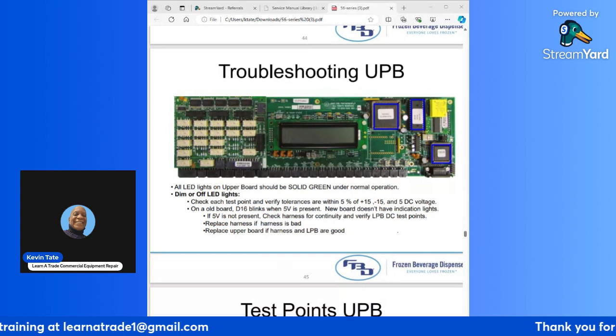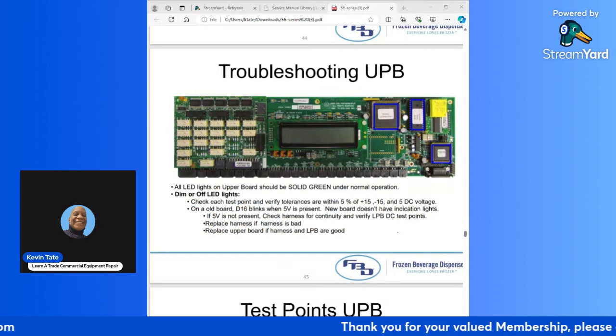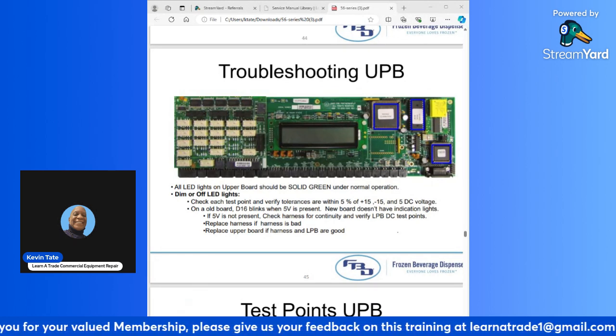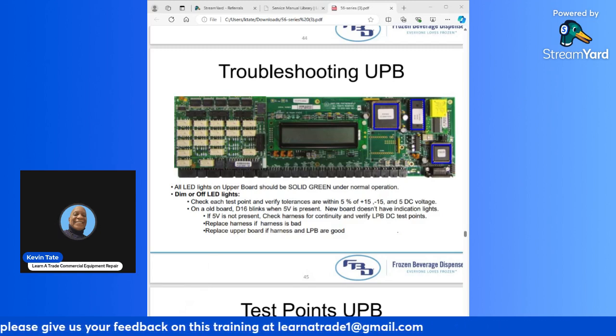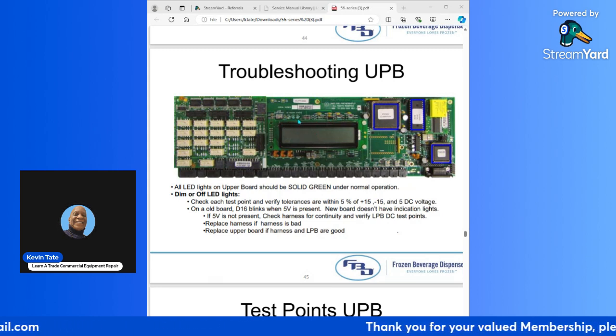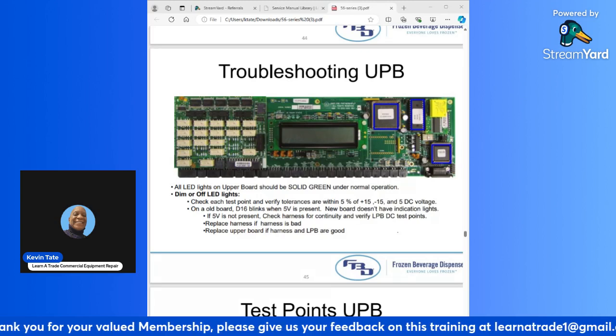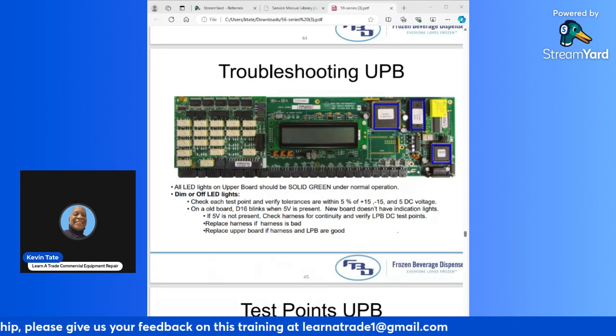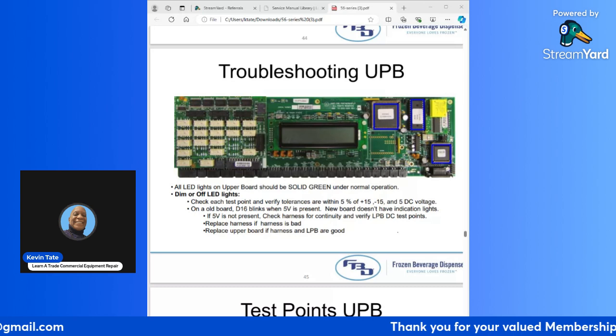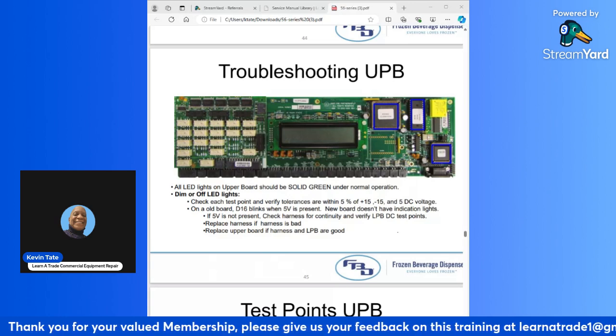All LED lights on the upper board should be solid green under normal operation. Dim or off LED lights: if you have dim or off LED lights on the board, you'll see those LED lights up top here. You should first check each test point and verify tolerances are within 5% of plus 15, minus 15, and 5 volts DC. On an old board, D16 blinks when 5 volts is present. New board doesn't have indication lights.